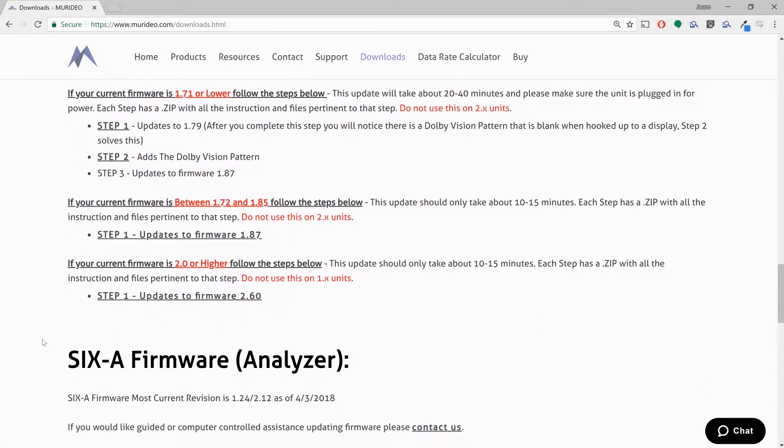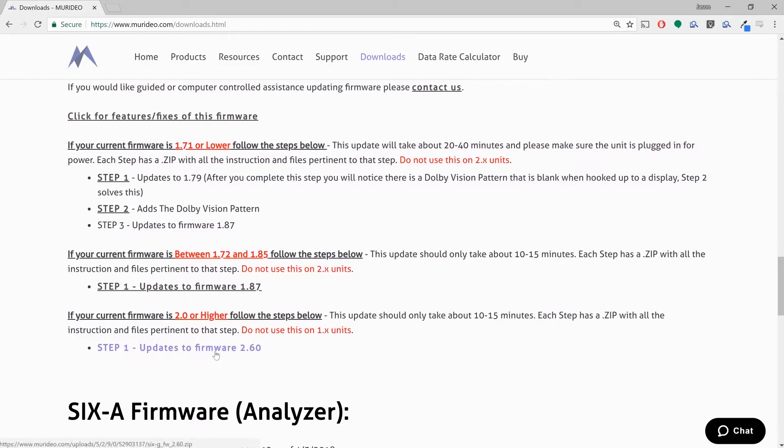Now if you do have a version 2, you can jump straight into firmware 2.60, which is what I'm going to do today. My Murideo generator is at 2.50 and I want to get it to 2.60. So what I'm going to do first is click on the link here for the download.